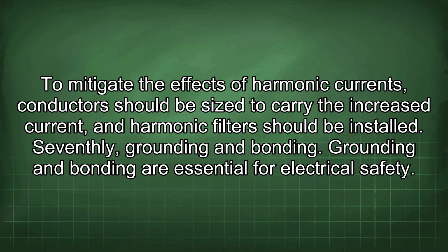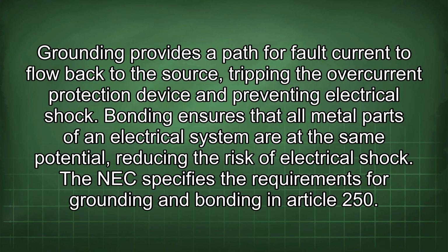Grounding and bonding are essential for electrical safety. Grounding provides a path for fault current to flow back to the source, tripping the overcurrent protection device and preventing electrical shock. Bonding ensures that all metal parts of an electrical system are at the same potential, reducing the risk of electrical shock. The NEC specifies the requirements for grounding and bonding in Article 250.